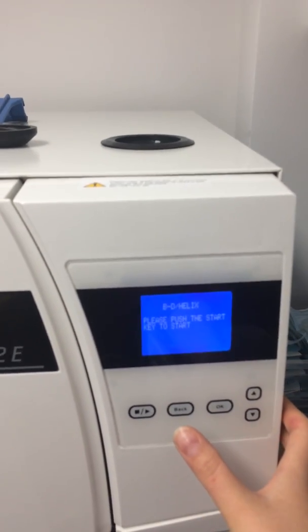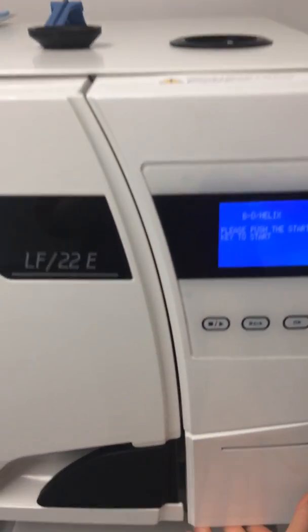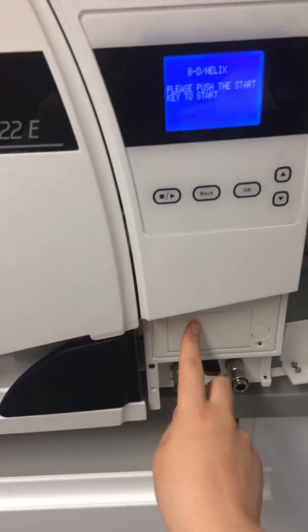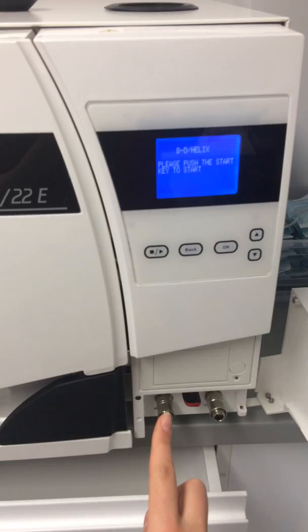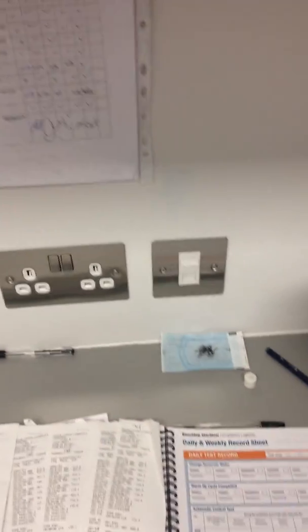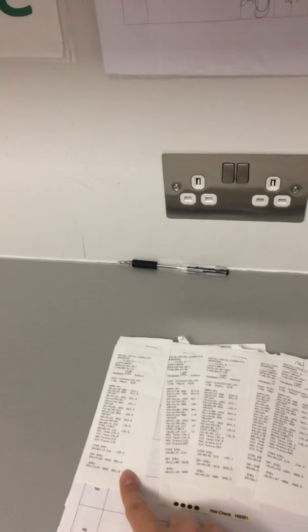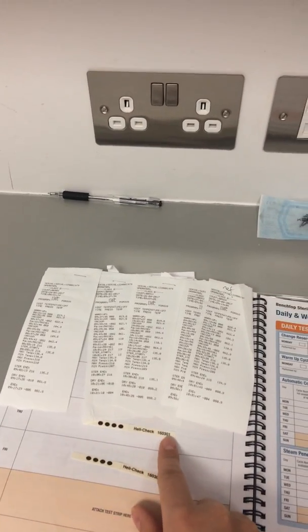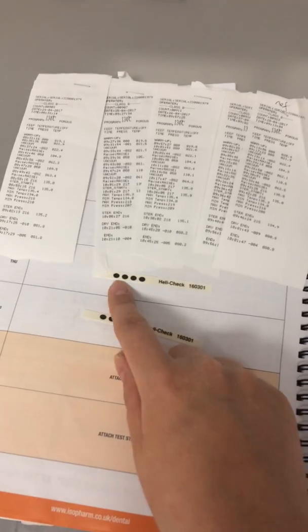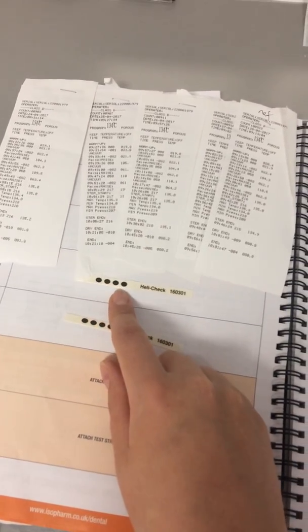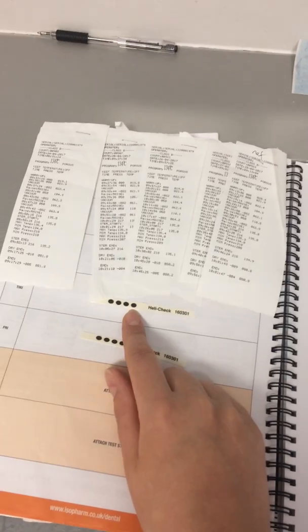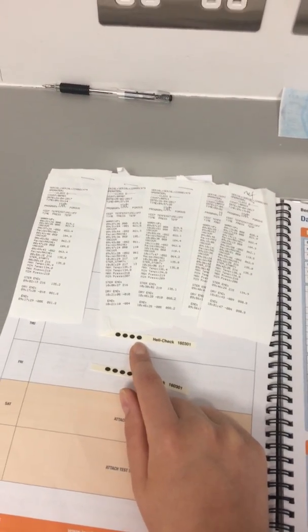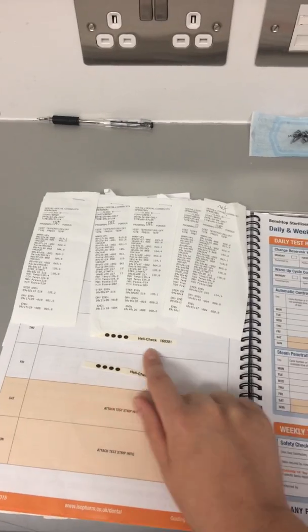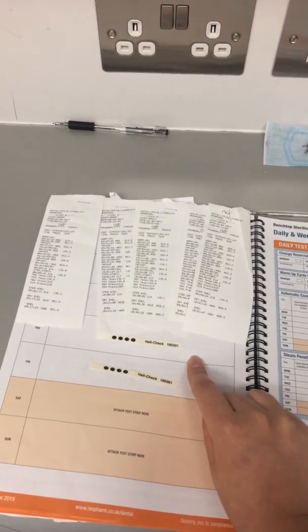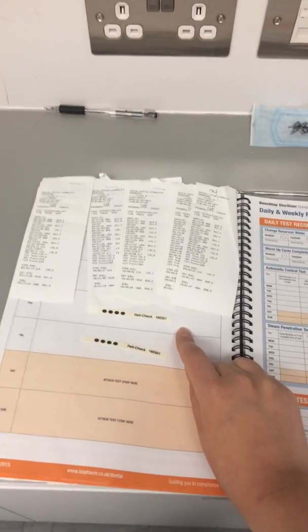We're not going to do it now because it will take around 13 minutes. I would like to show you the rest of the functions. As soon as the cycle is complete, you will see a printout coming out. You have to attach that printout to the logbook. As you can see here, there is a printout from last week, and we attach the test strip. A complete test strip has to change color totally from pink to black. If it is a bit blue, reddish or brownish, it means the steam penetration test didn't go well and we have to redo the cycle or call the engineer for further advice.